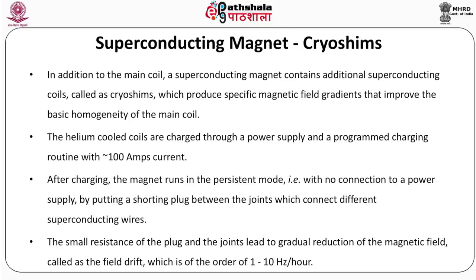In addition to the main coil cooled in liquid helium, a superconducting magnet contains additional superconducting coils called cryoshims, which produce specific magnetic field gradients that improve the basic homogeneity of the main coil. The helium-cooled coils are charged through a power supply and a programmed charging routine with approximately 100 amps current. After charging, the magnet runs in the persistent mode with no connection to a power supply. This is done by putting a shorting plug between the joints connecting different superconducting wires. The small resistance of the plug and the joints leads to a gradual reduction of the magnetic field, called field drift, which is of the order of 1 to 10 hertz per hour.